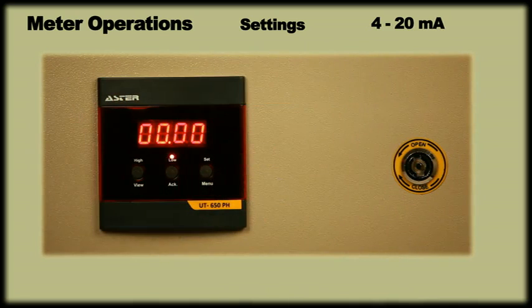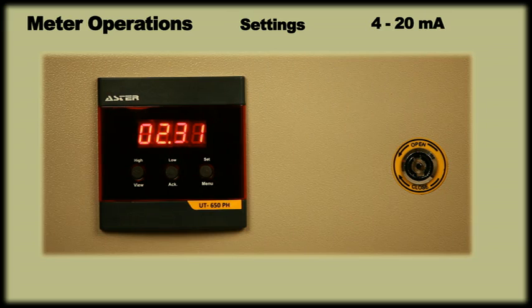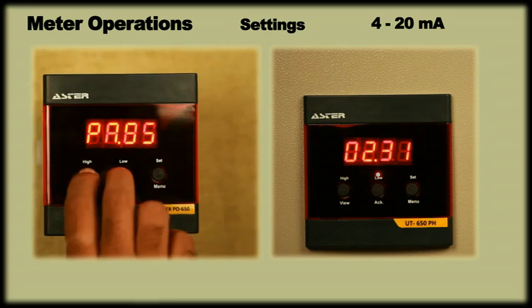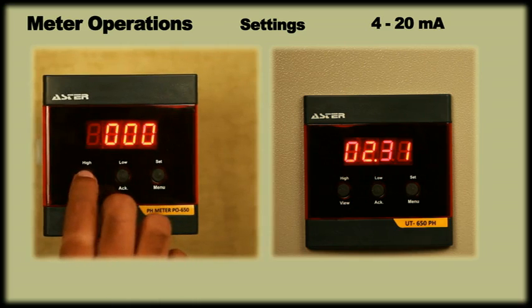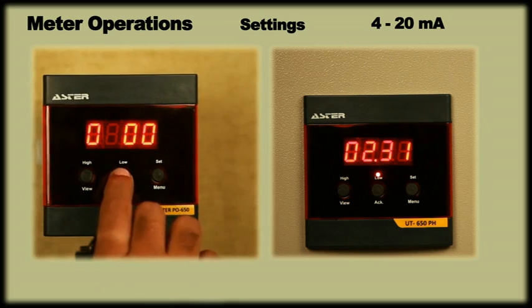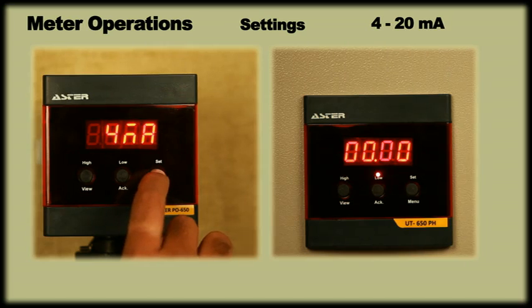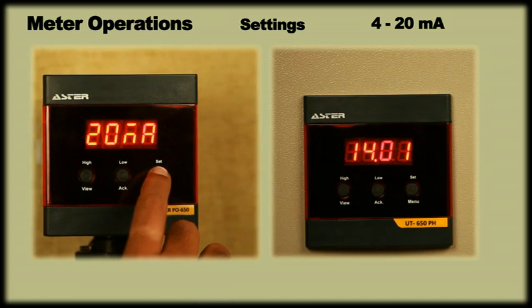Note, the meter has an inbuilt 4 to 20 mA output simulator for easy synchronization with the PLC or any other remote device. To output standard 4 and 20 mA, enter password 0420. Press menu twice to output 4 mA. Press ACK key and then menu key to output 20 mA and press menu twice to exit.